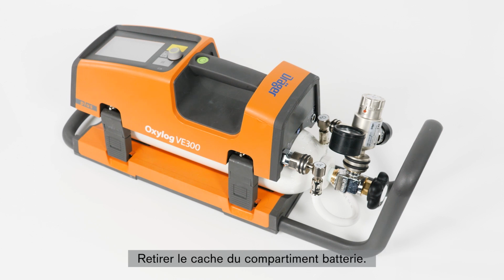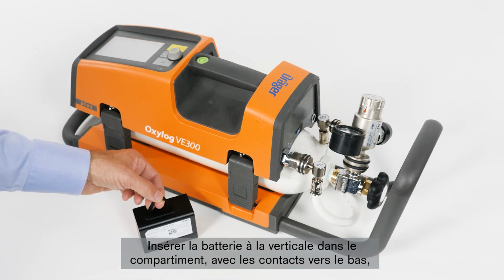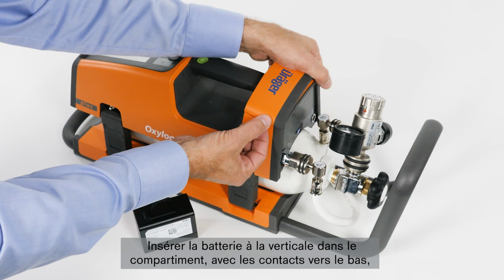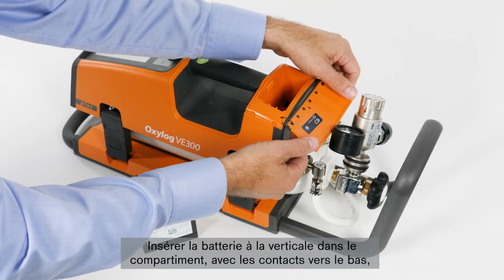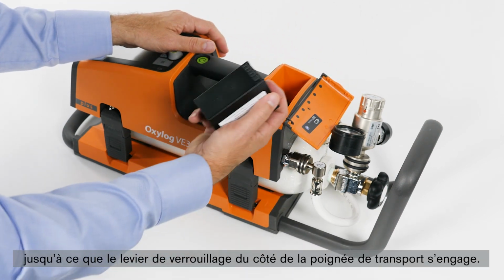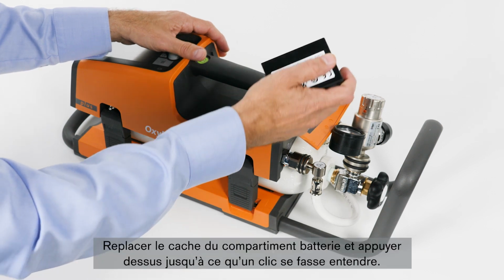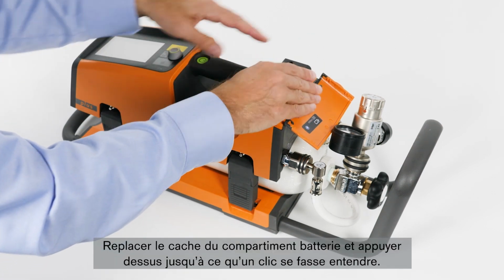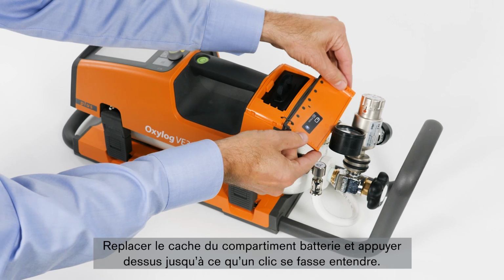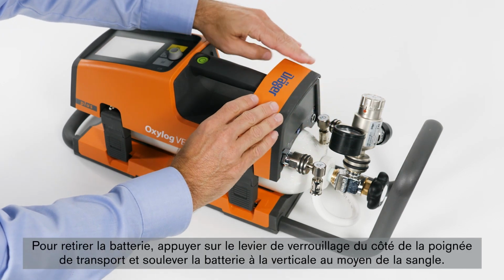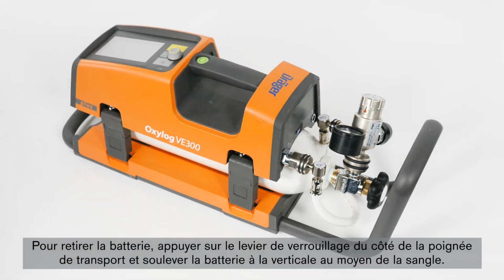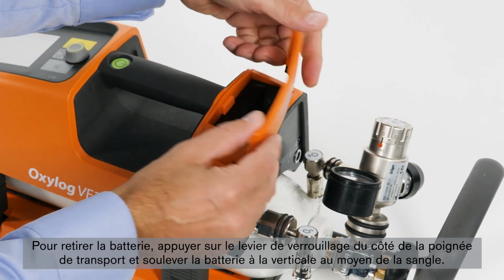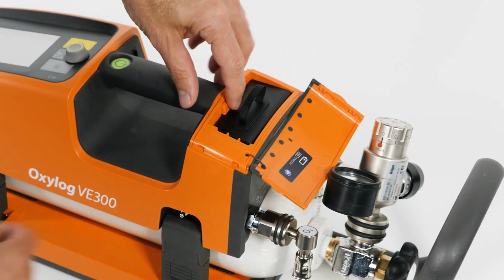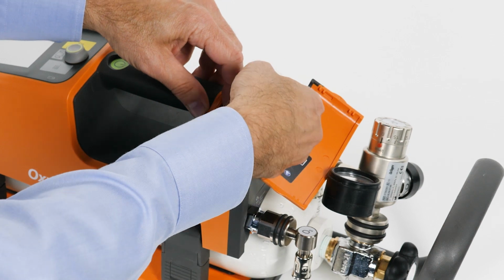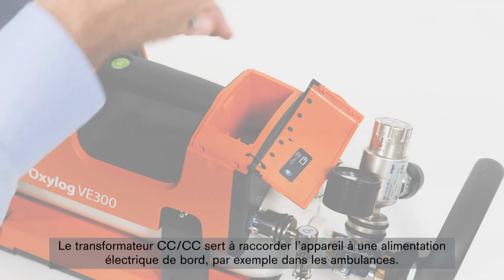Internal power is provided by means of a removable, rechargeable battery. Remove the battery compartment cover. Insert the battery vertically in the battery compartment with the contacts facing downward until the locking lever on the carrying handle side engages. Fit the battery compartment cover and press it until it engages audibly. To remove the battery, press the locking lever on the carrying handle side and lift out the battery vertically using the strap.